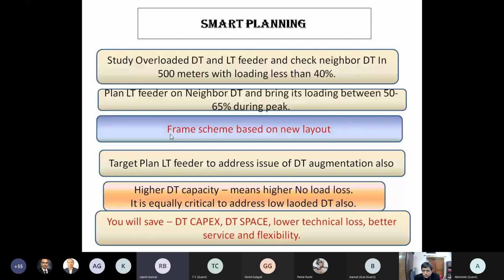What I have realized is, if you have more wire, it is better than having more transformers, because at least wire has no load loss. And if you have more feeders, more parallel feeders, you are dividing the current. So look into that direction rather than looking at assets which have higher no-load loss. And definitely, if you install more DTs and other equipment, then you need more space too.